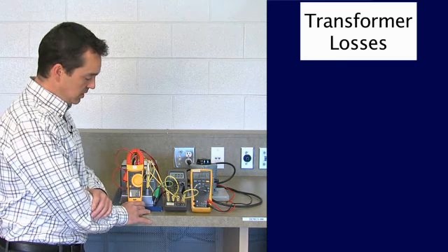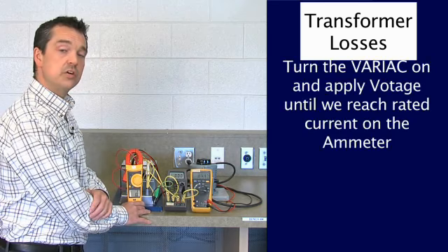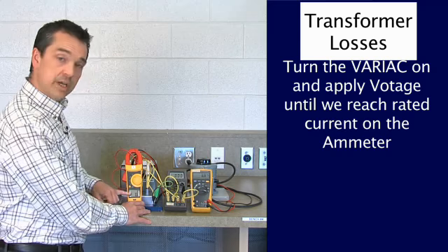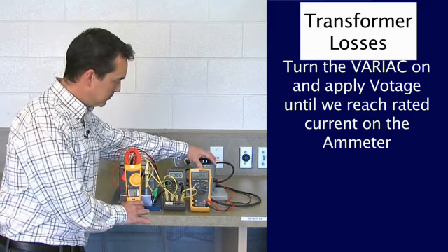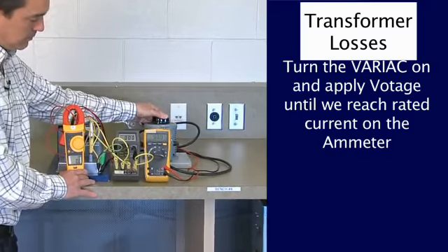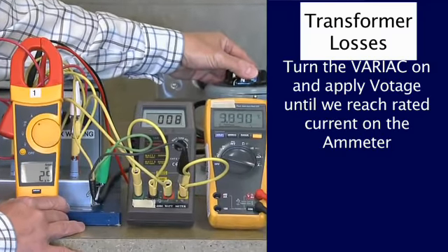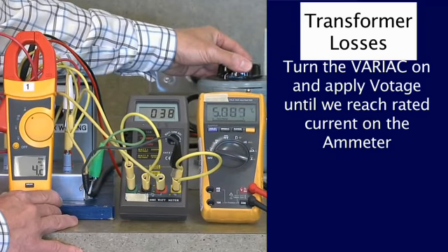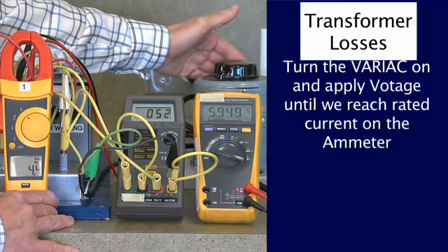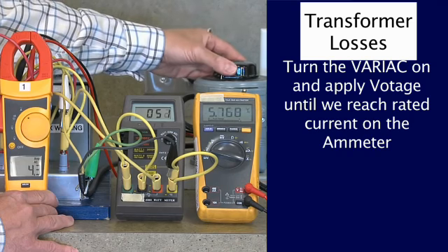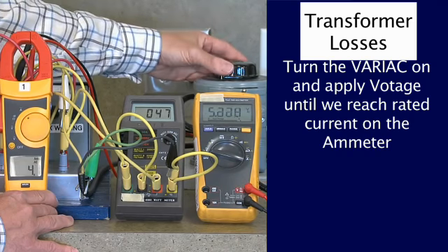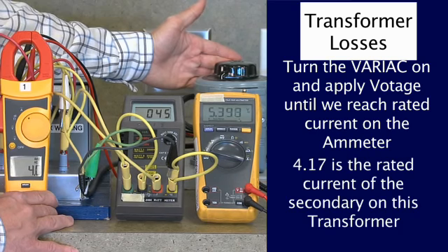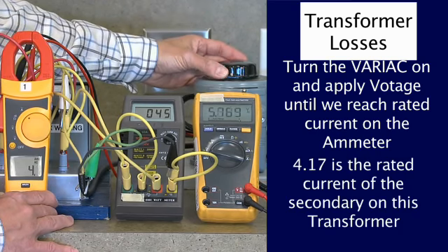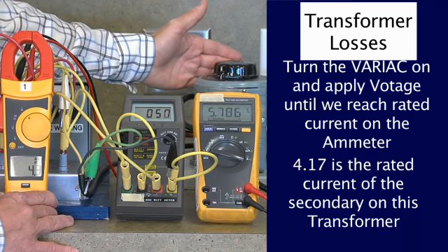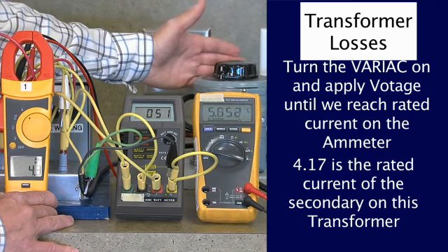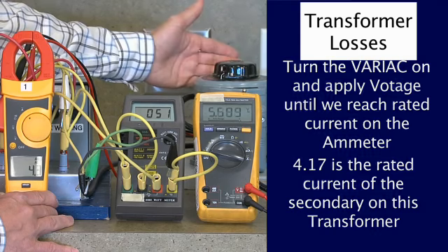So what I'm going to do is turn the variac on, we'll start to apply voltage to this, and we'll get up to rated current on my ammeter. And I haven't moved this a whole bunch, and we're already climbing like crazy. So 4.17 is the rated current of the secondary of this transformer. I've got my ammeter here at about 4.2. Pretty tough to get it to sit right on there. So it's close to 4.2 amps.